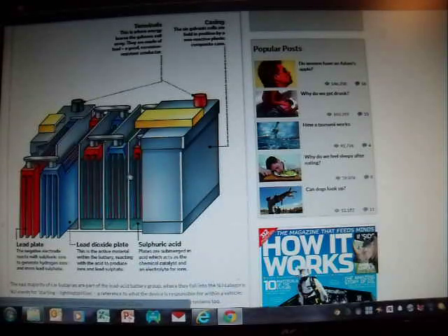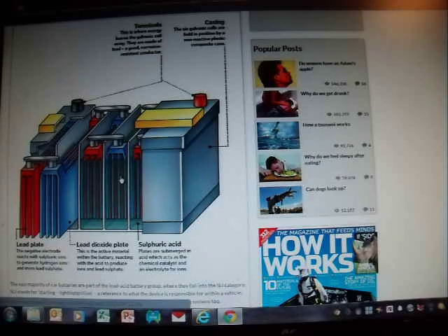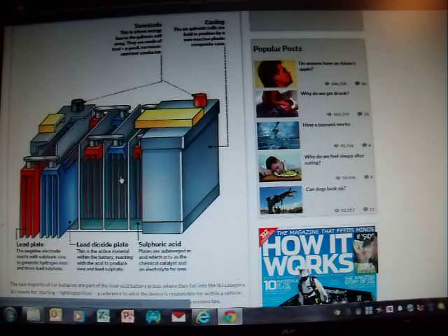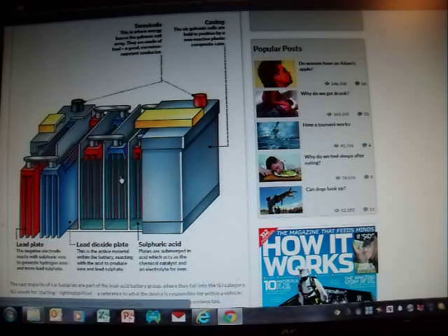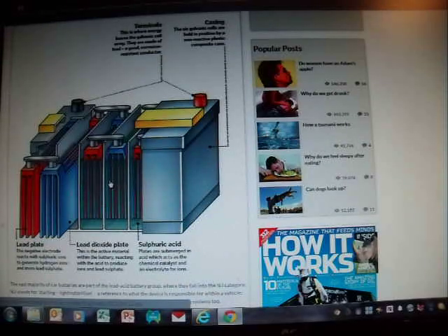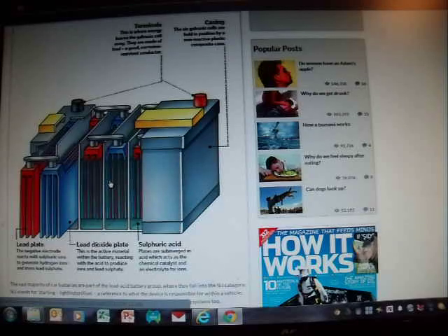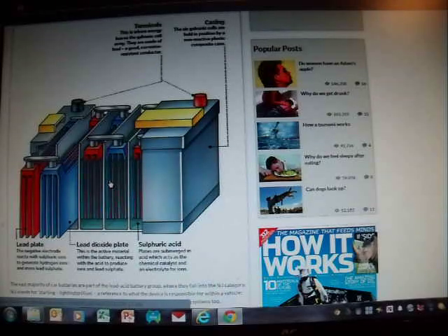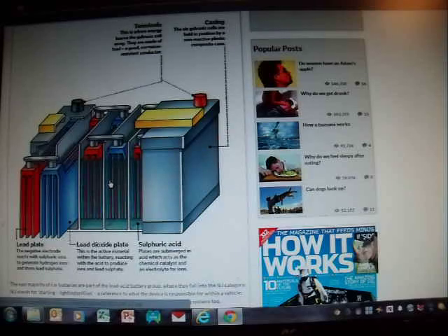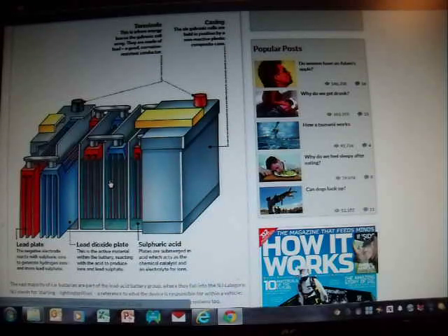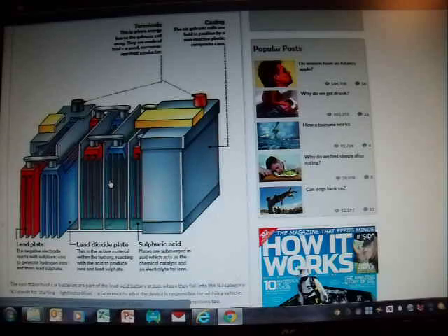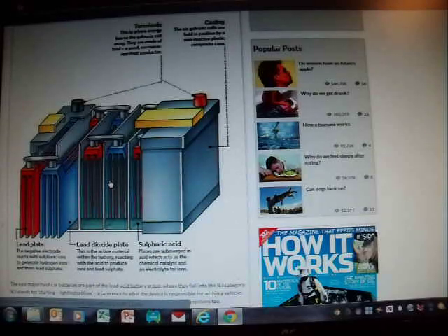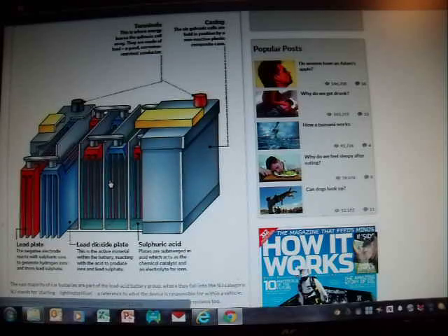The deep cycle batteries have much thicker plates. They'll last a lot longer because as you go through discharge and recharge cycles, some of that lead is going to be converted into, it's going to oxidize in some ways and it's going to sulfate. And so your battery loses power over time because of the exhaustion of the lead plates. And so the thicker the lead plate, the longer the battery is going to last.